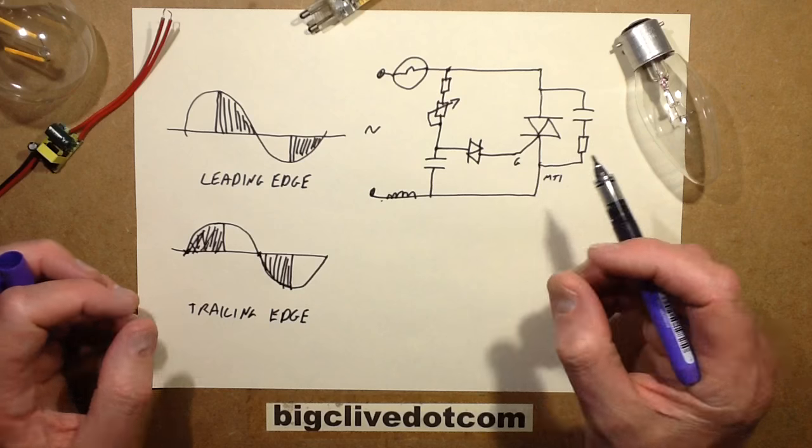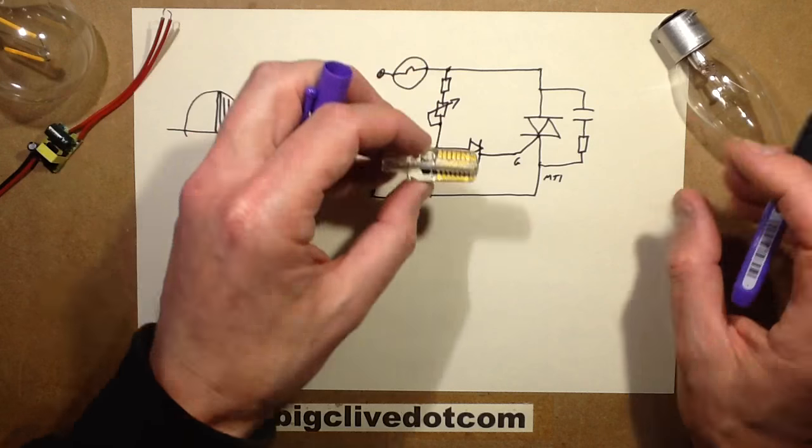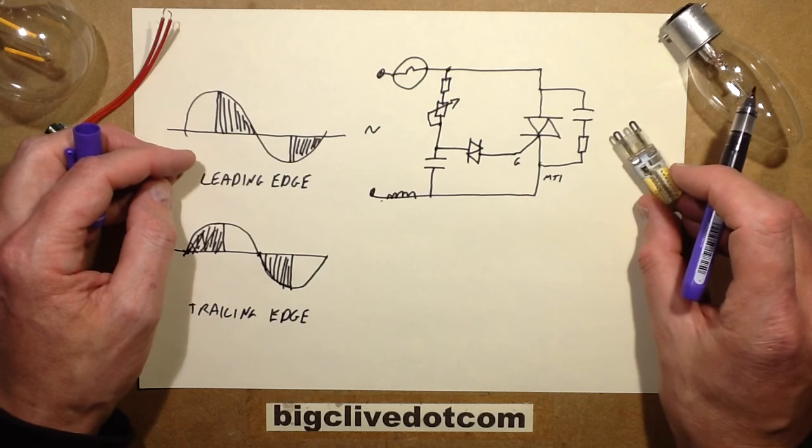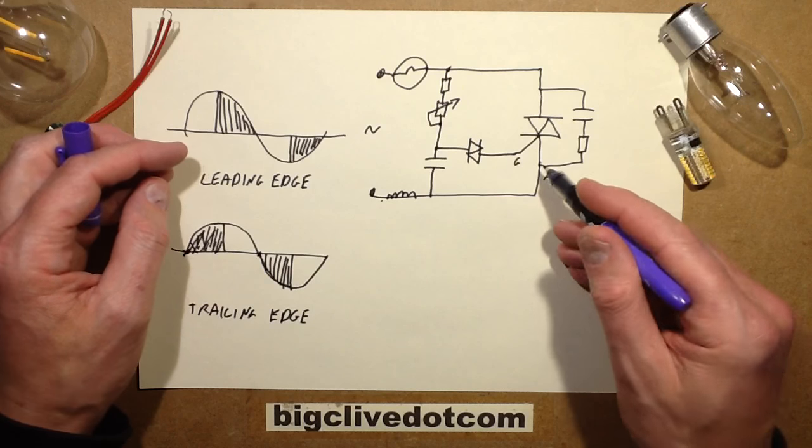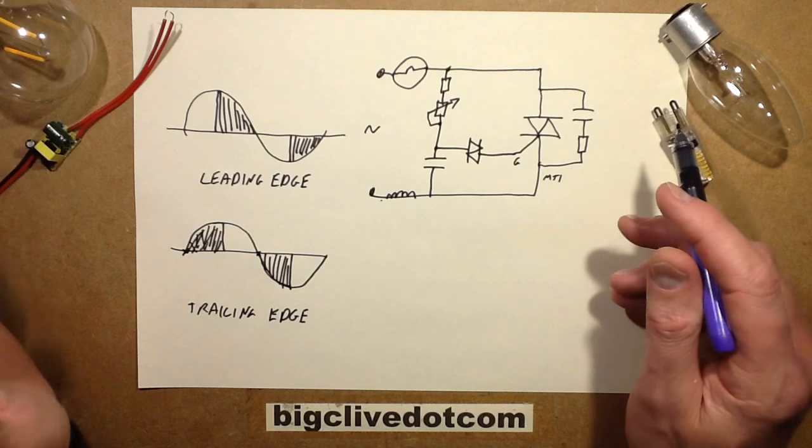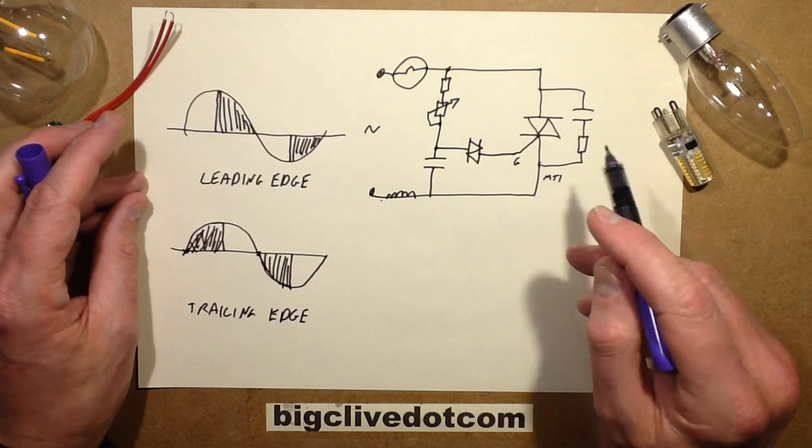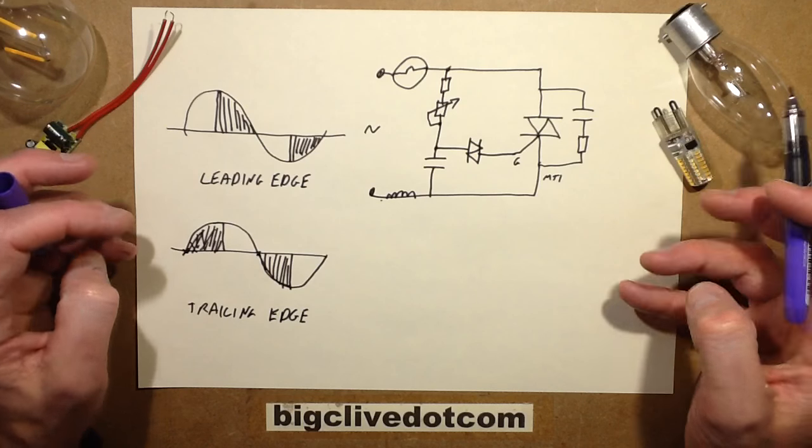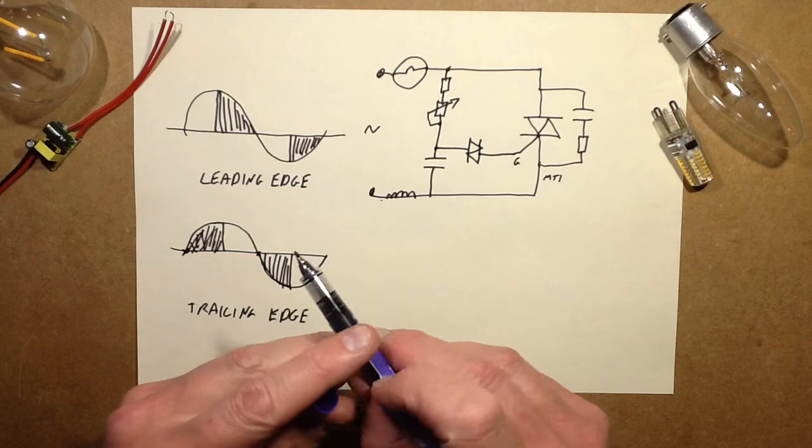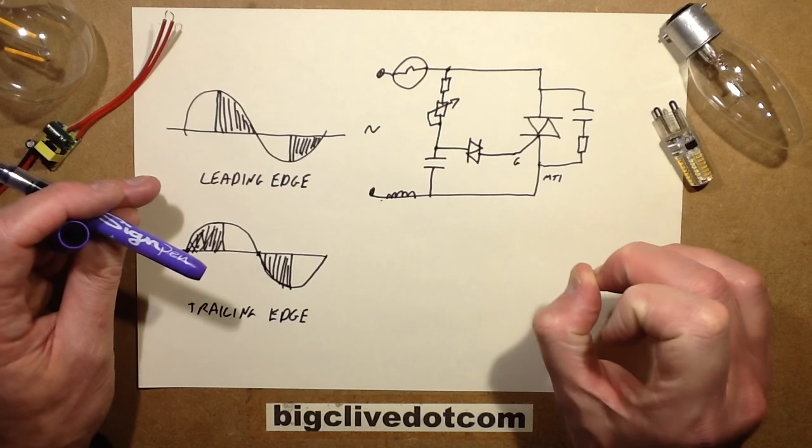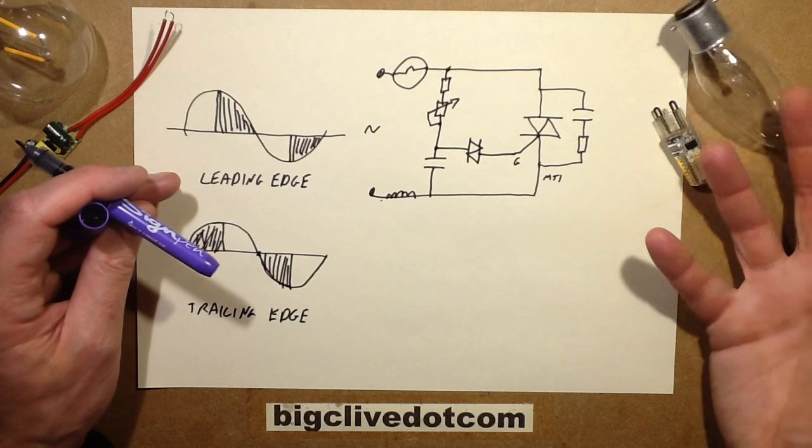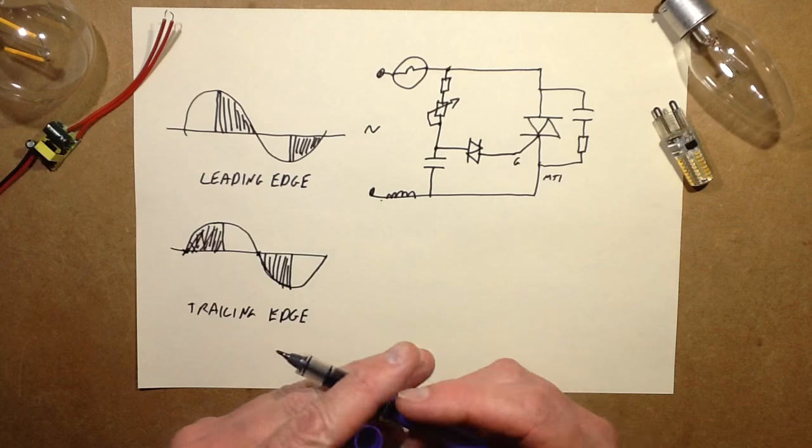However, when we use LED lamps with these dimmers, a problem occurs. Firstly, you have to have a minimum load to make these dimmers latch, and it's not so much a problem with the trailing edge dimmers, but with the old leading edge dimmers with the triacs it was a problem. Without that load, the triac won't latch and all you'll get is a very dull glow because the triac is getting its trigger pulse and then it's just instantly turning back off again because there's nothing to hold it on.